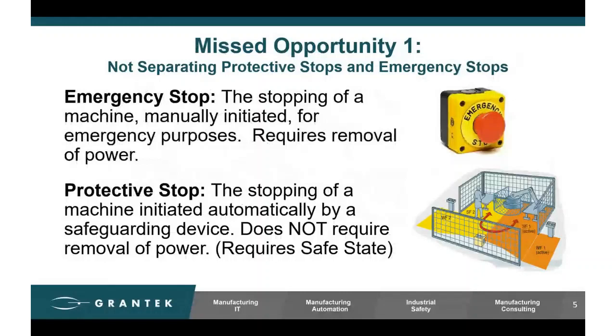So we'll start off with the most technical, diving into the weeds of safety circuit design. I want to talk about the missed opportunity of not separating out your emergency stops and your protective stops. Let's start with definitions. An emergency stop's purpose is to remove power from all elements of the machine that cause motion or harm. This can either be done by immediately removing power, like unplugging the machine from a wall, or doing a controlled stop and then removing power. But no matter what, an emergency stop has to remove power. A protective stop, on the other hand, has an entirely different purpose: its purpose is to put the machine in a safe state, which doesn't necessarily mean you have to remove power. And that's where the missed opportunity is.